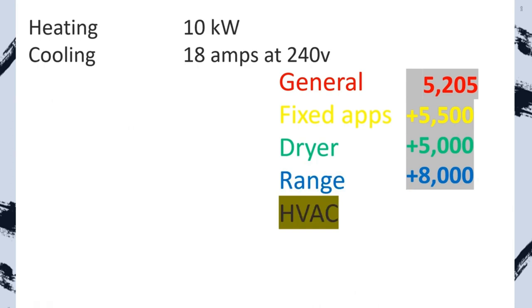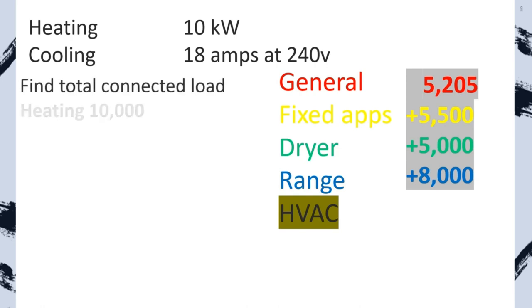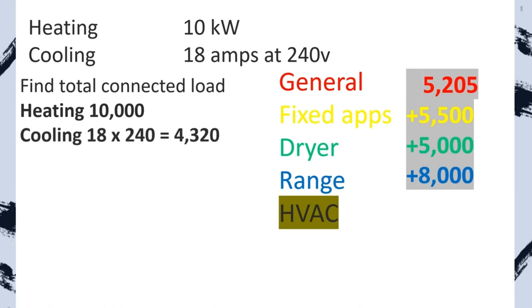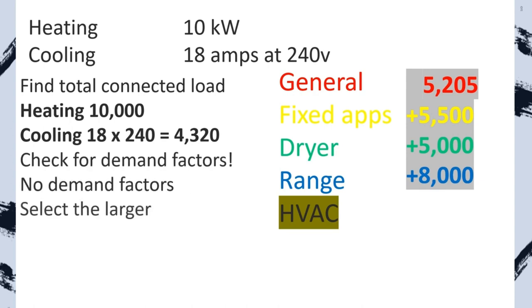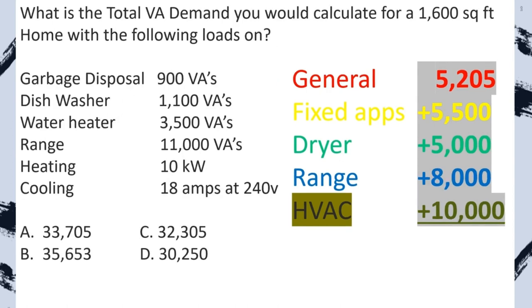For HVAC VAs: take the larger of heating or cooling. Heating is 10,000 VAs; cooling is amps multiplied by volts equals 4,320 VAs. No demand factors on this portion — select the larger: 10,000. Now total everything together: 5,205 plus 5,500 plus 5,000 plus 8,000 plus 10,000. Push equals between each addition to avoid calculator errors, and always double-check your answer. We end up with 33,705 and select A.